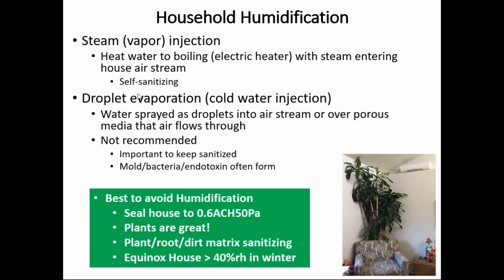Both of these need to be maintained for scaling and scum and other stuff forming in the reservoirs. But the cold water especially can be a breeding ground for things like molds, mildews, bacteria, endotoxins, and you need to keep on top of it. And so keeping it sanitized is extremely important. Several studies have shown that these cold evaporators are very large generators of endotoxins, and our report on endotoxins will familiarize you more with their detrimental effects. So it's best to avoid humidification.